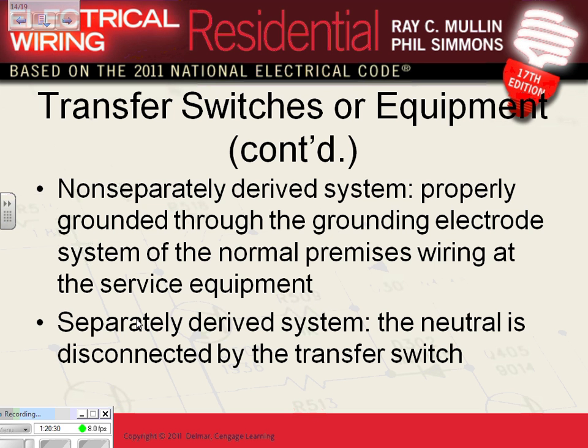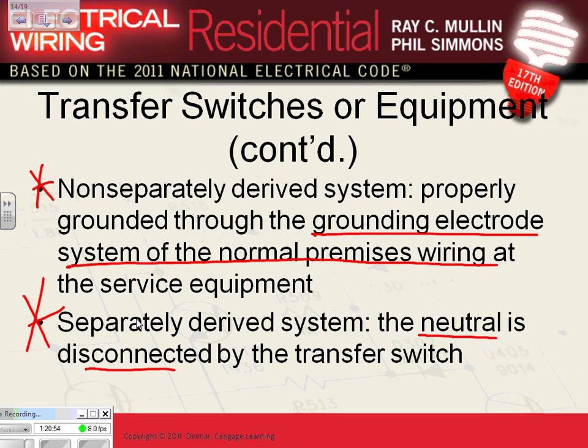Non-separated, this is interesting. Please, if you want to highlight this one for me: nonseparately derived system and separately derived system. Non-separately derived system, properly grounded through the grounding electrode conductor system of the premises wiring. This is the key point. The neutral is grounded through the service. Separately derived system, the neutral is disconnected by the transfer switch and grounded right at the generator. These two terms, if you guys know them, will help you a lot as a designer, a lot.